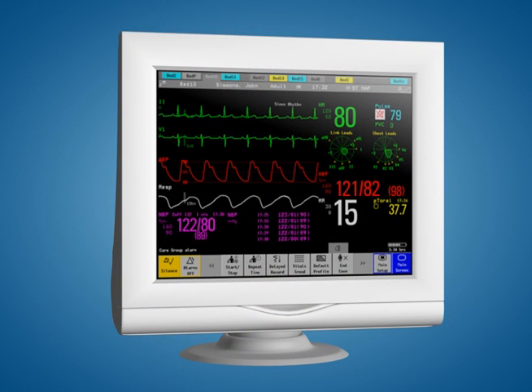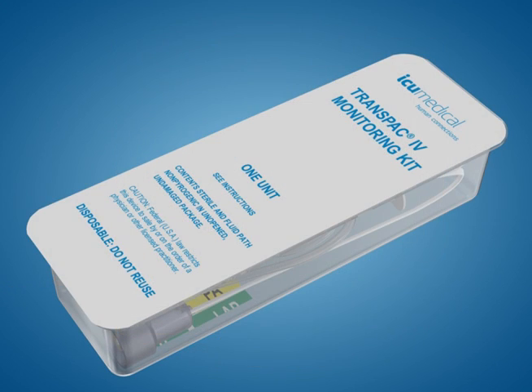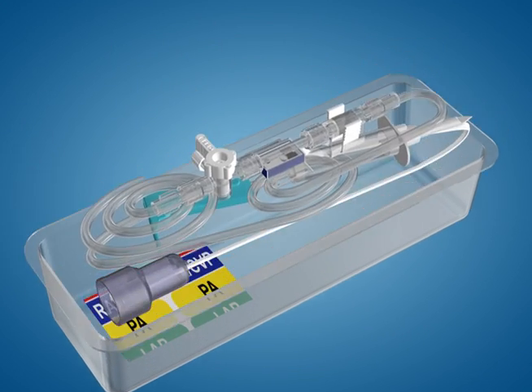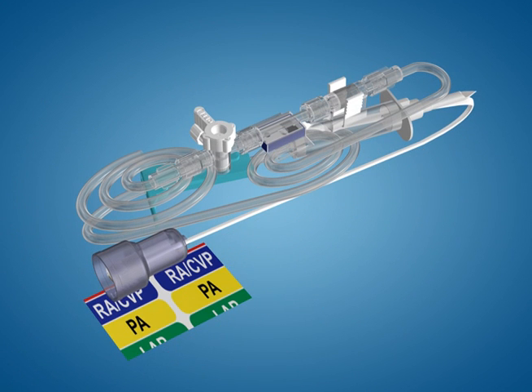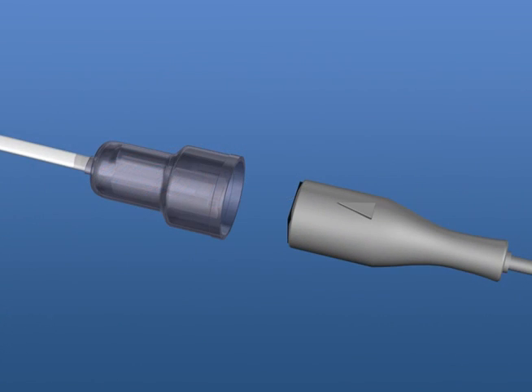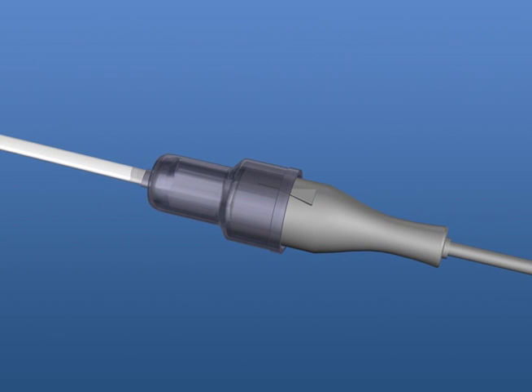The first step is to turn on the patient monitor so it can warm up. Make sure that the reusable cable is properly connected to the monitor and that the connection is clean and dry. Using aseptic technique, remove the kit from the package and gently tighten any connections that might have come loose during shipping. Attach the cable from the pressure transducer to the cable from the monitor by matching the arrow on the reusable cable with the embossed line on the Transpac 4 connector boot and pressing until you hear a click. The plastic boot protects the connection and it has a positive lock so it won't accidentally disconnect.